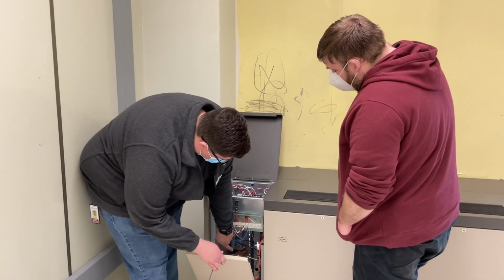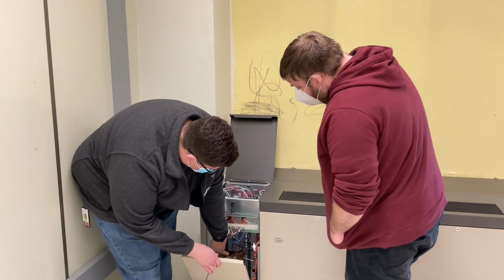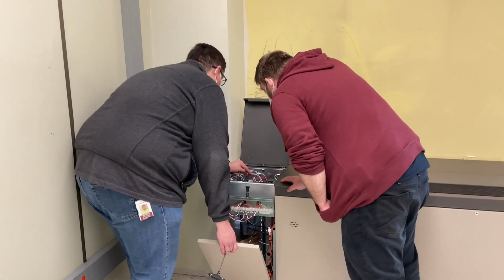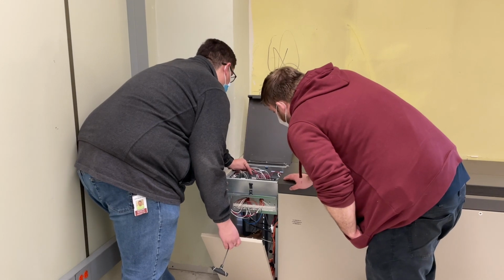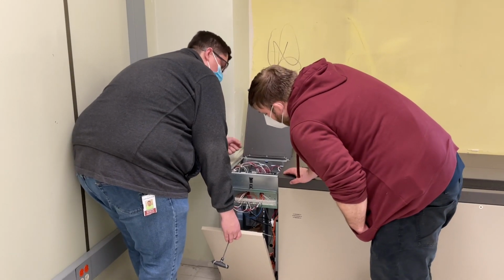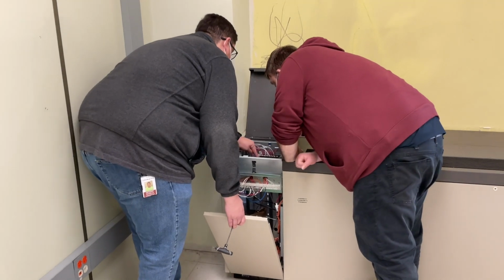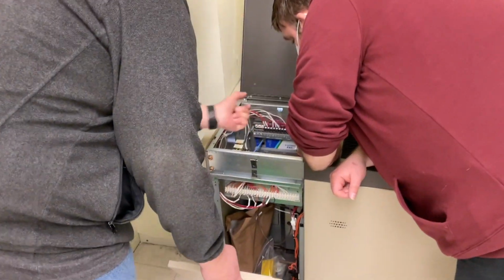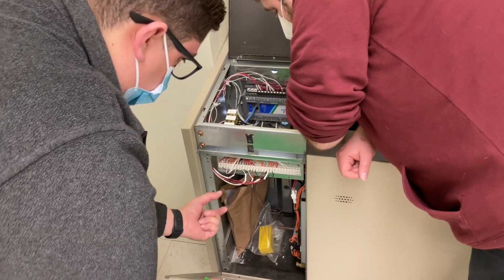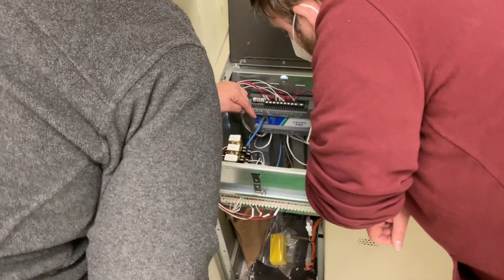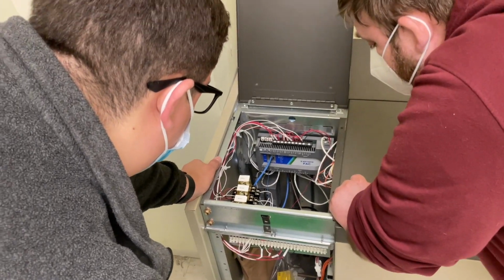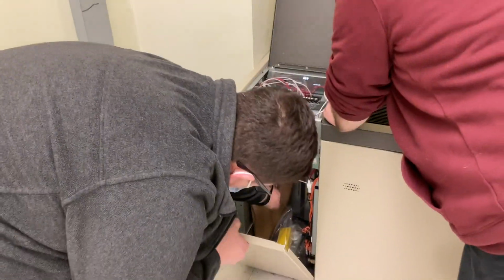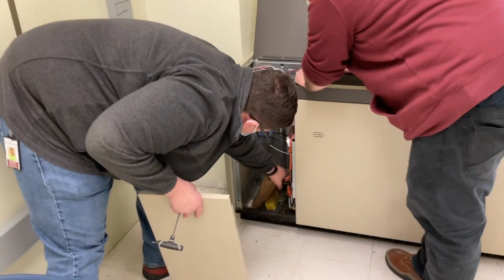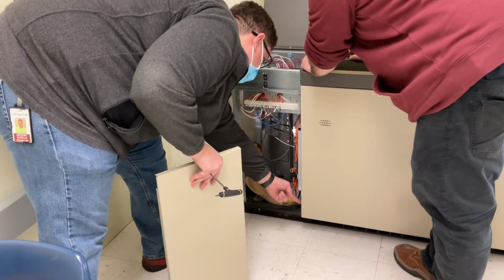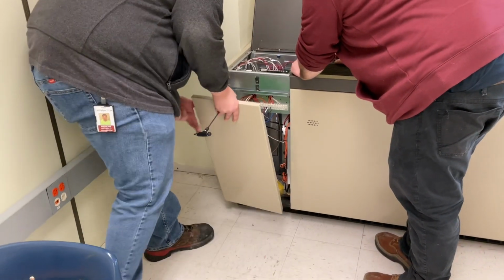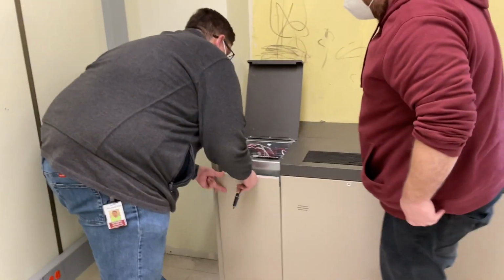Now the mixed air damper access, you can see right there. So we're controlling that actuator in the bottom there. And if that's ever loose or anything, there's actually a little Allen key in the back that you can use to loosen that damper. I don't know if you can see that plastic part right there. Yeah, that's around there. And then also filter status is this gray box back in here. You see this right here? This section goes to the ports here. So you got one on the low side and one on the high side of the filters. That's that.